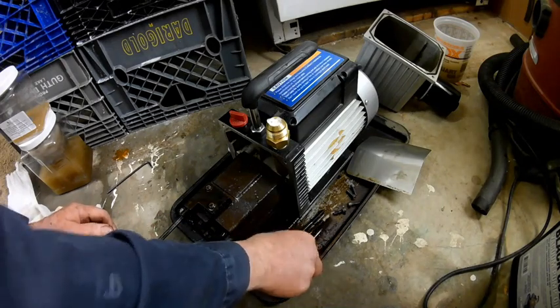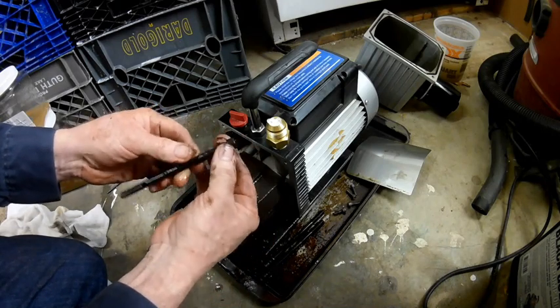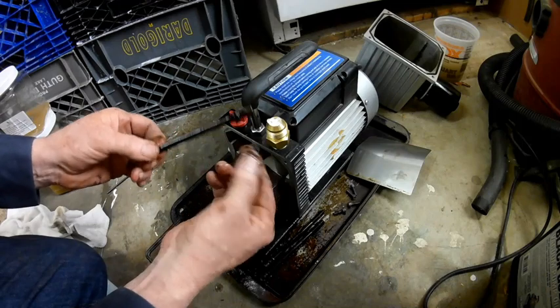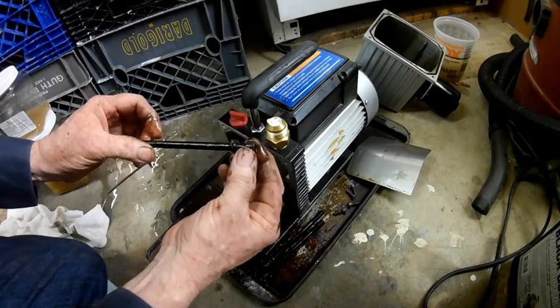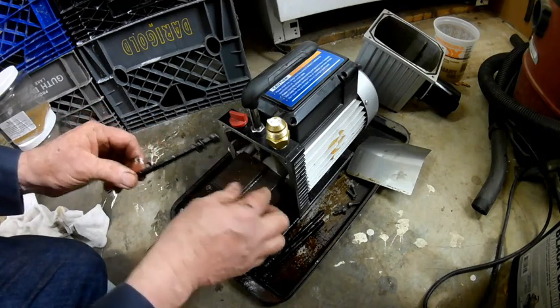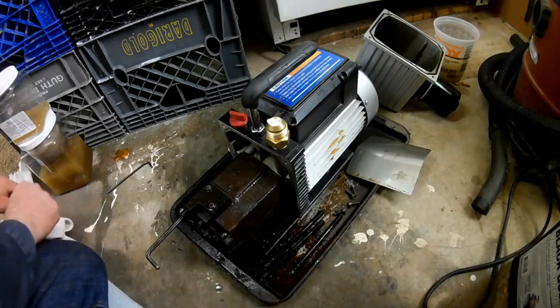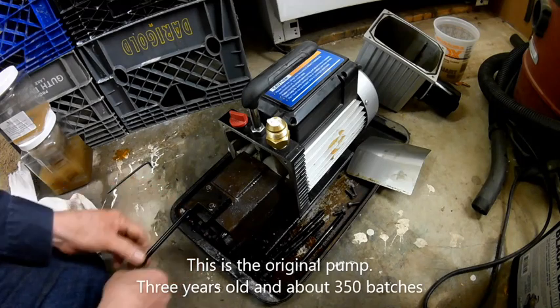I've noted there's a black kind of coating on these bolts, and that could be normal wear and tear from the vanes inside the pump wearing out. But it could also be rust, which is common because there is water that gets trapped inside. This definitely looks rusty right here, and it could just be from the water that the vacuum pump sucks in during the freeze drying cycle. I guess this is par for the course.